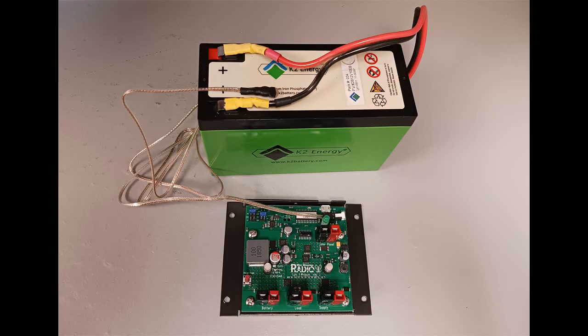An optional temperature probe can be used to control charging based on the battery's temperature. If the temperature of the battery is too high or low on a lithium iron phosphate battery, the Epic PWRgate will cease charging the battery. For lead-acid batteries, the Epic PWRgate will adjust the charge voltage depending on the battery temperature. This allows for the most optimum battery charging.